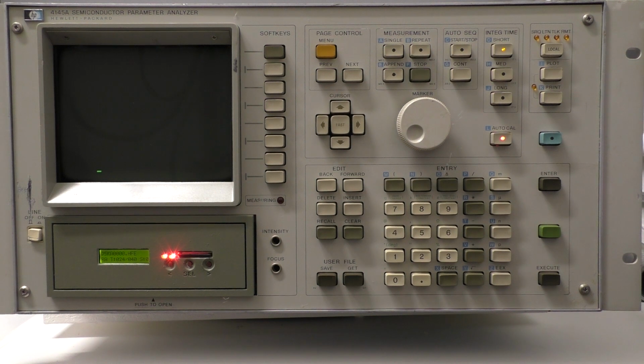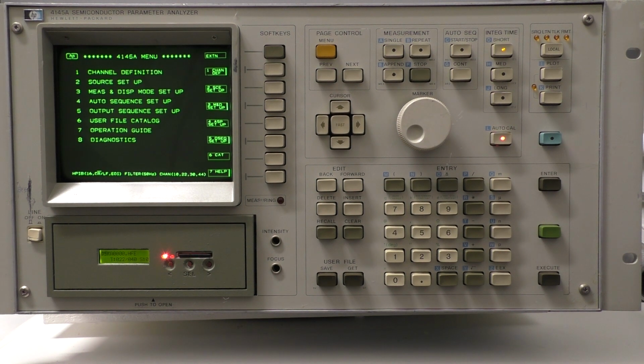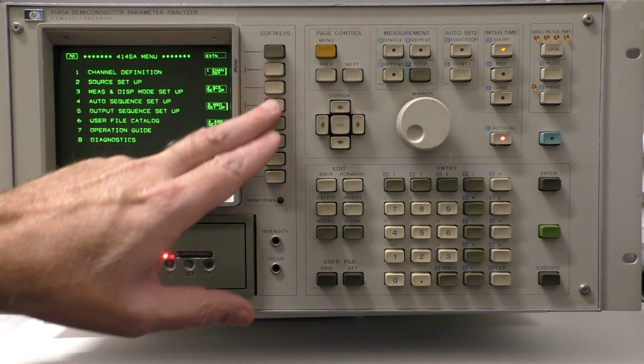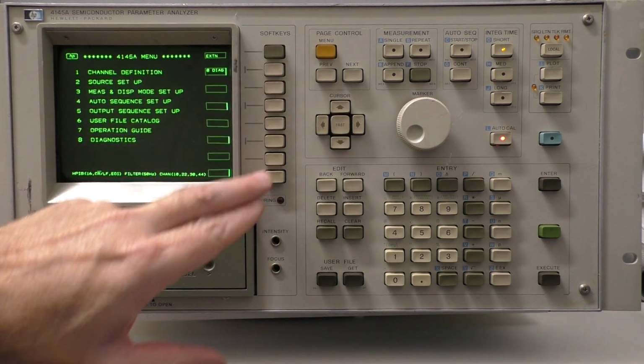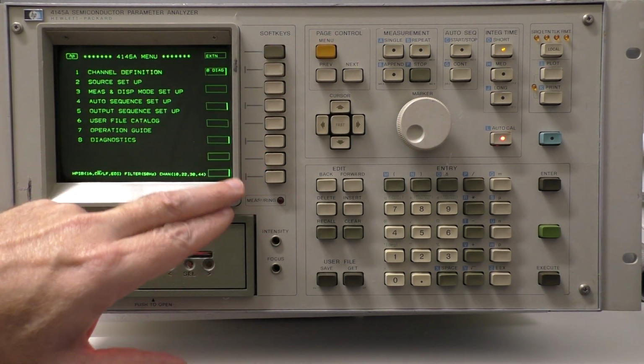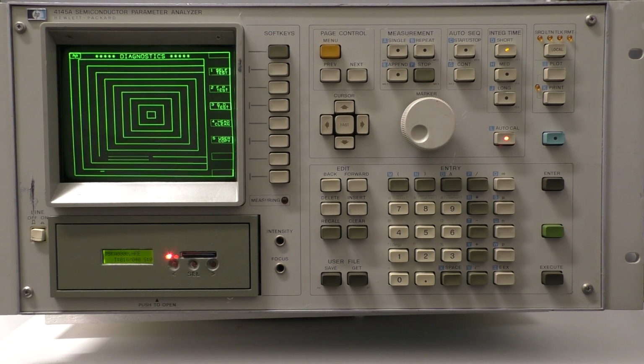Fire up the unit. We have a perfectly aligned and crisp display. Let's perform a graphics self-test. Press extension. Press option 8, diag from the menu. Press 3, graphic test. Perfect, we have a perfectly aligned pattern with the 2 dim strokes bottom left.